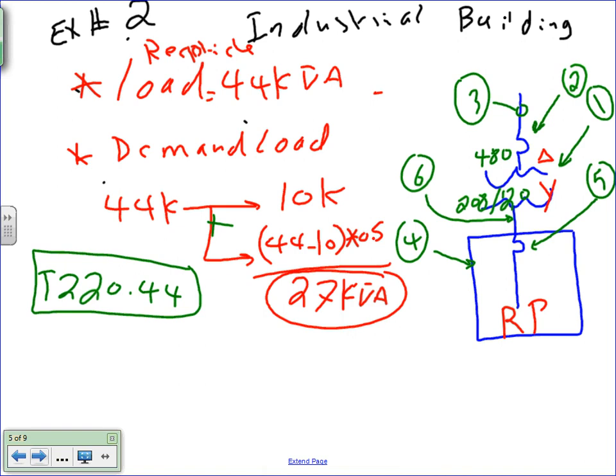They call it demanded. What's demanded versus connected? This number here, guys, is called connected load. Connected load is just all these receptacles added together. Demanded load is taking into consideration that it's highly unlikely that all of them are plugged in and sucking 180 volt-amps out of the system as we assumed. So we demand them. Can I get you guys to understand the stuff in the red here?